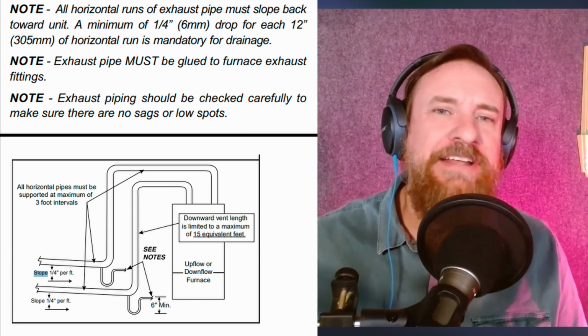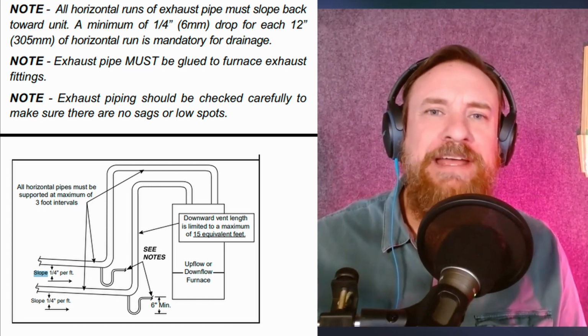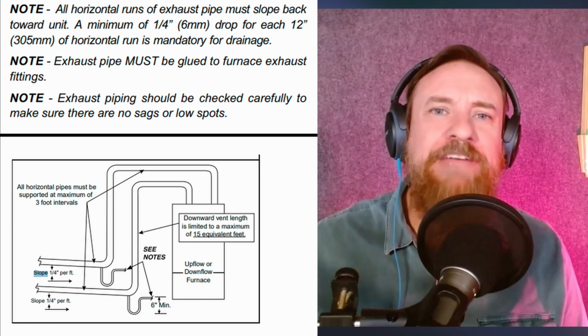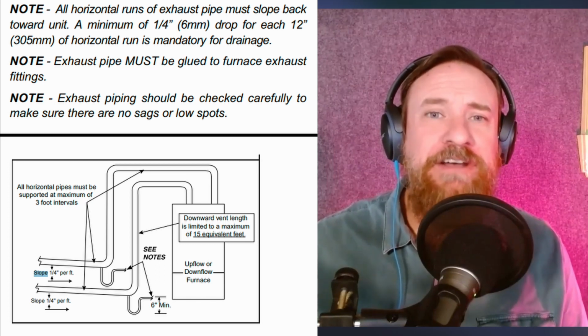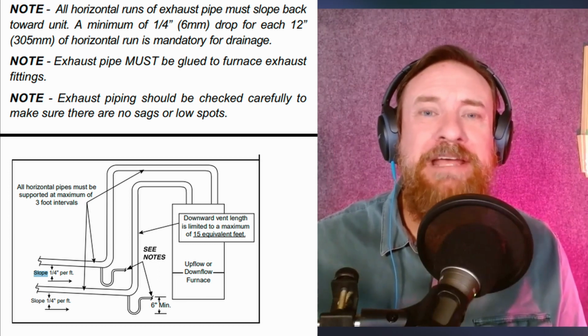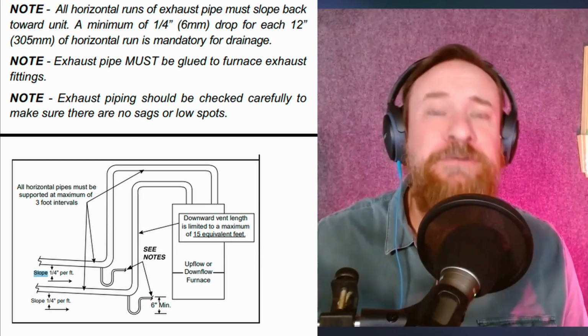Then the third person that came out said, hey, the flue pipe is actually sloping away from the inducer motor. What was happening was condensation was building up in the flue pipe and it was acting as a trap, and then the furnace wasn't working right and ended up burning out the inducer fan motor. So again, it goes back to that installation manual.